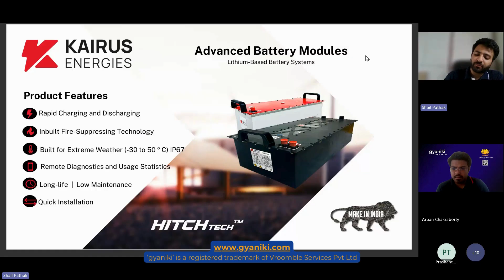Lithium cells have to be maintained in a temperature zone of 25 to 40 degrees Celsius for optimum efficiency, achieving 92 to 95% efficiency and a minimum of 5,000 life cycles. If you go below 25 degrees, you will find dendrite formation and lithium plating, which will reduce the life of the battery.